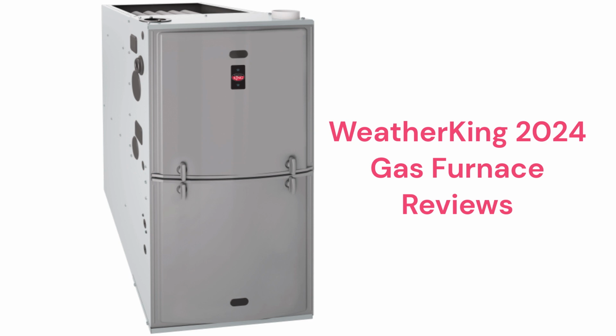They use aluminized steel primary heat exchangers which resist corrosion but are not as durable as brands that use stainless steel. The units use direct spark ignition, which is louder and less reliable than brands that use hot surface ignition.